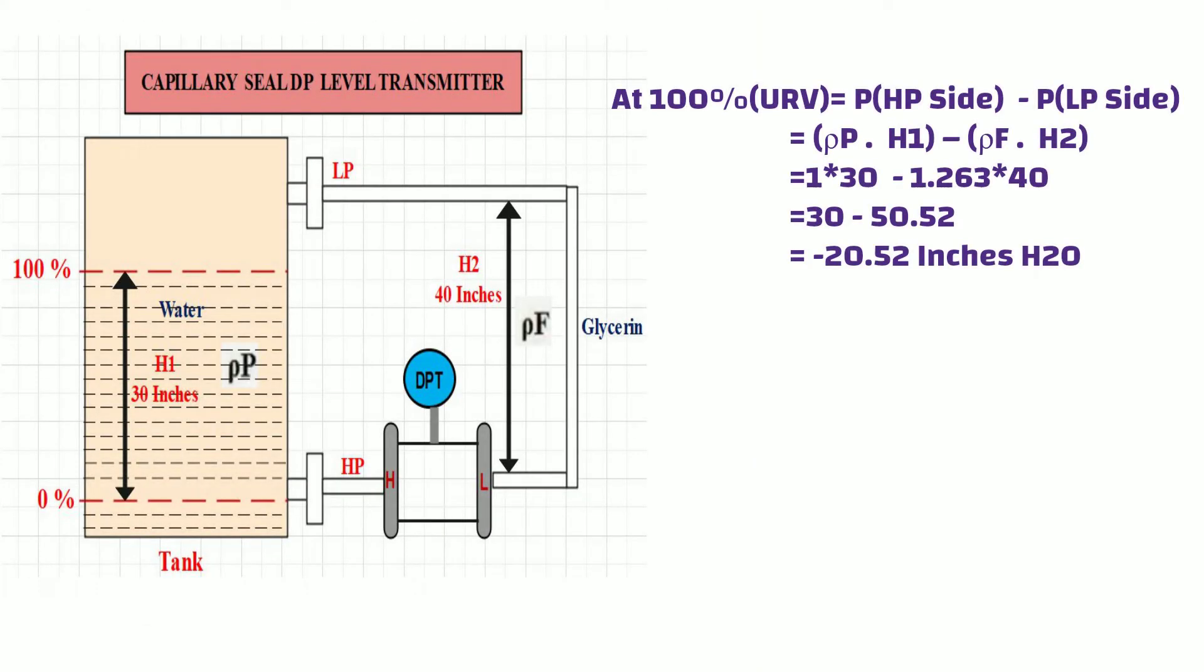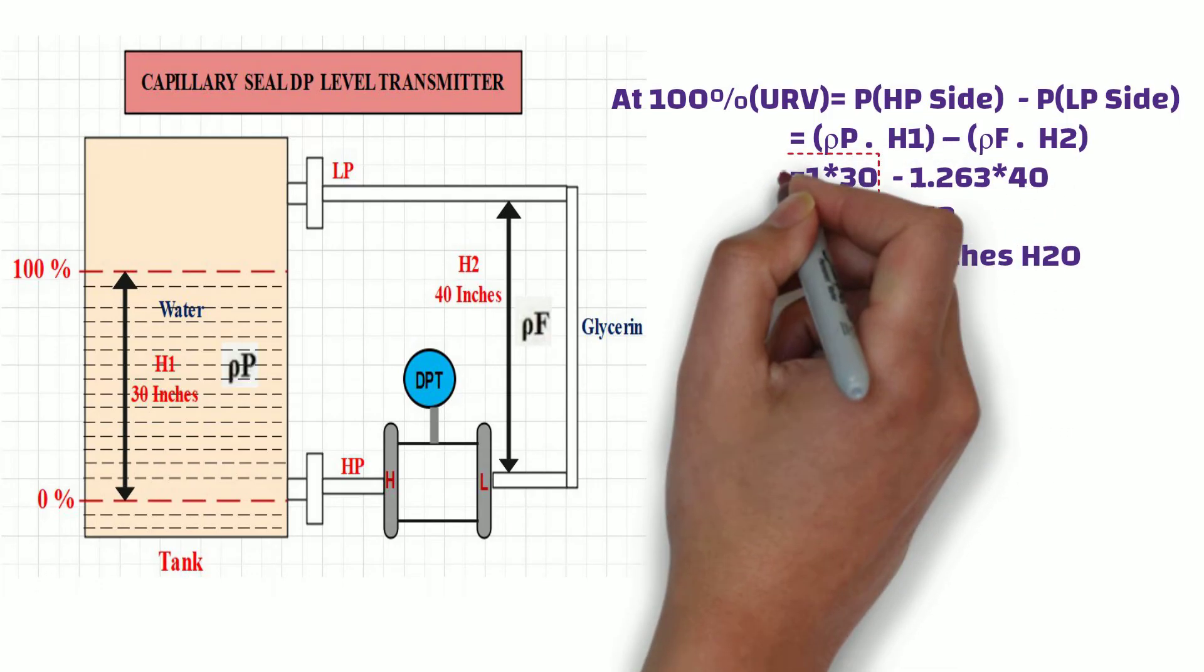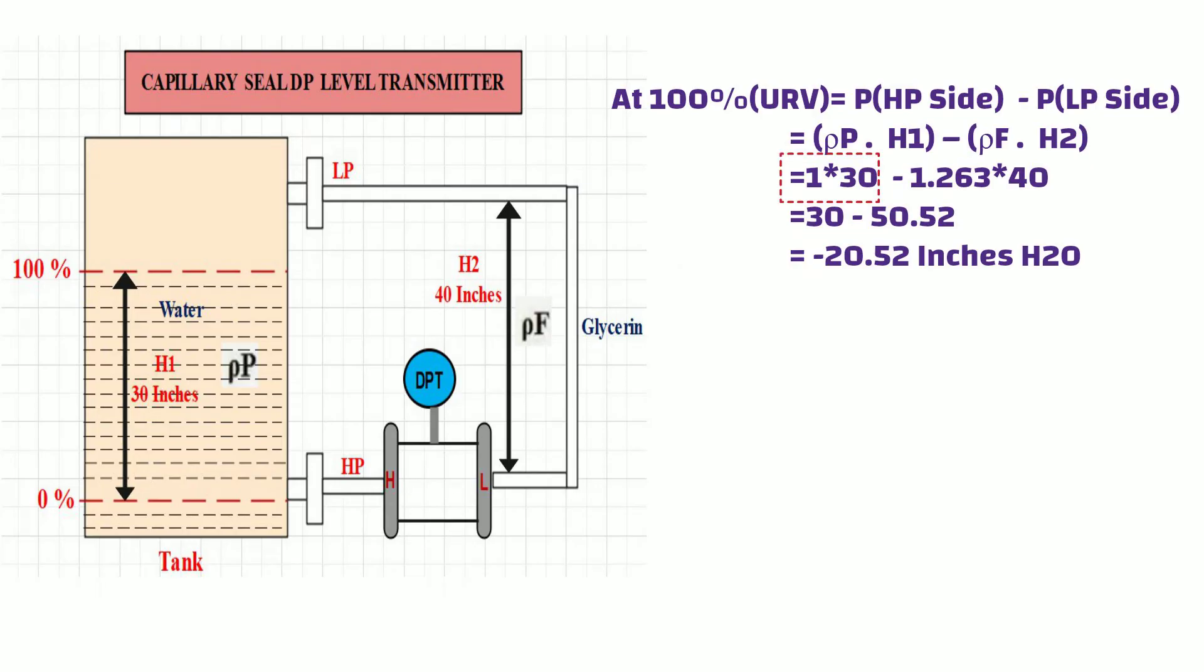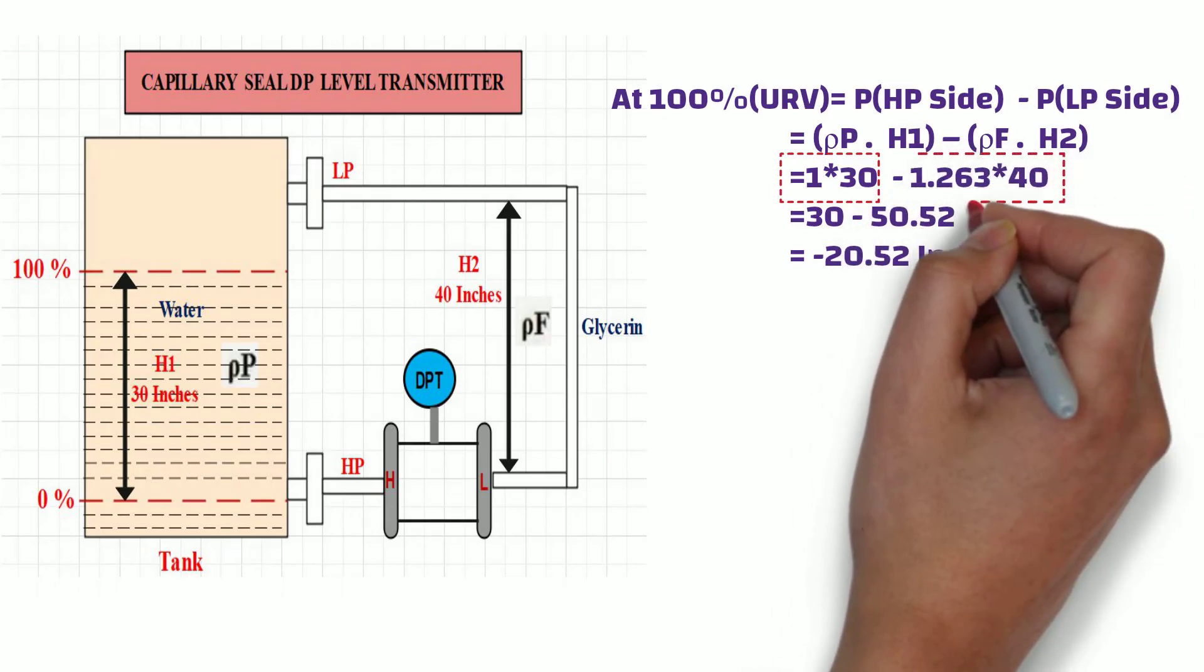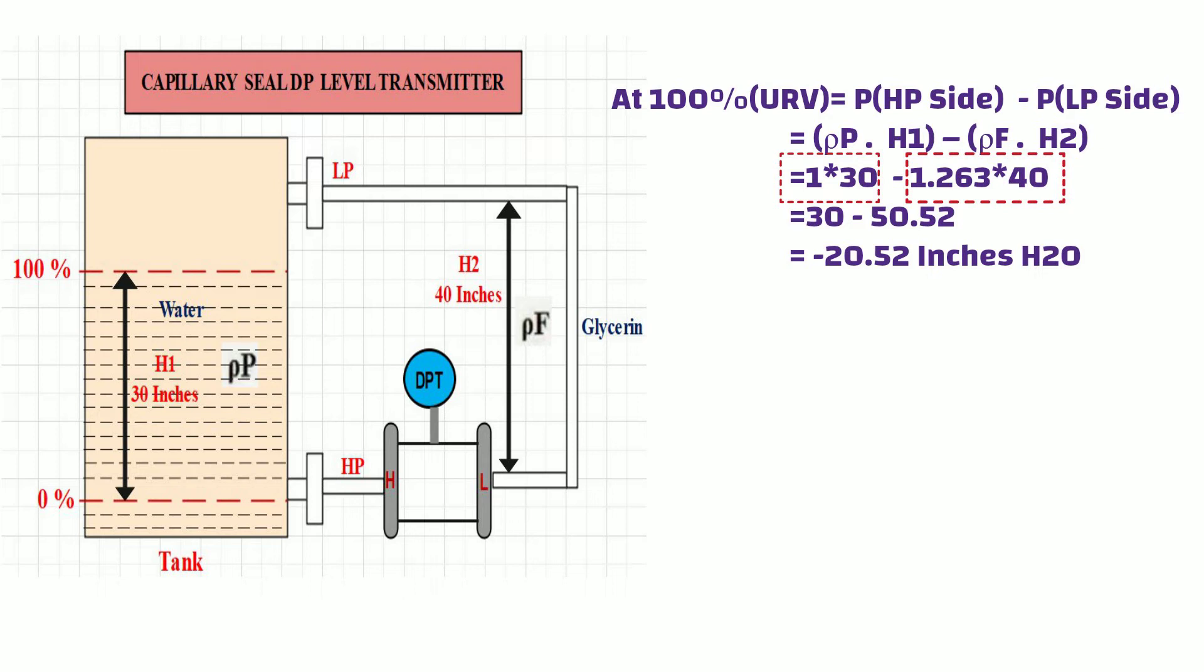Similarly, at 100% level or at maximum level, the DP transmitter's high port side has 30 inches H2O pressure, which multiplies with the specific gravity of water, which gives 30 inches H2O. At the same time, the DP transmitter low side has 40 inches H2O pressure, which multiplies with the specific gravity of glycerin, which gives 50.52 inches H2O pressure. So the differential pressure is minus 20.52 inches H2O at 100% level. And this is our upper range value in this example.